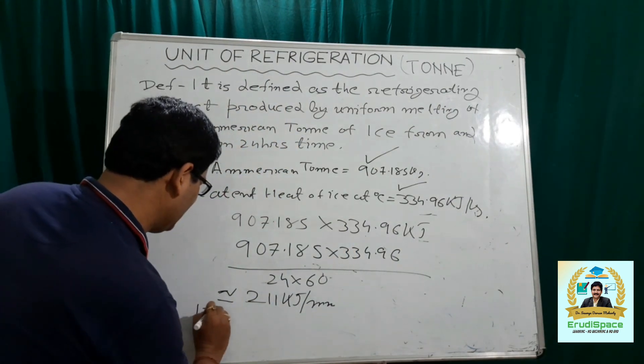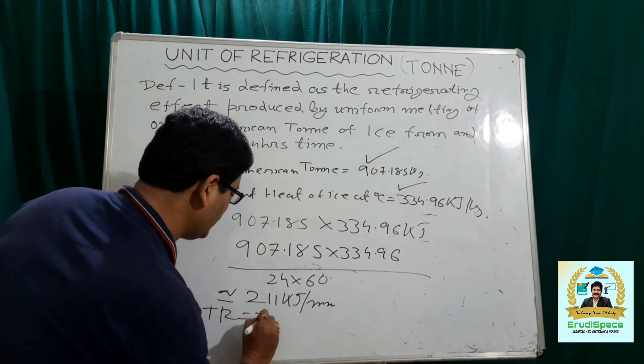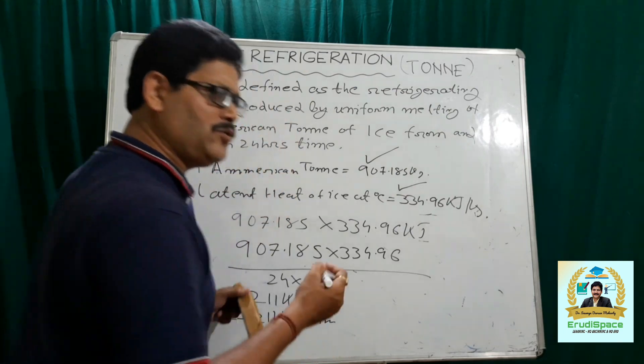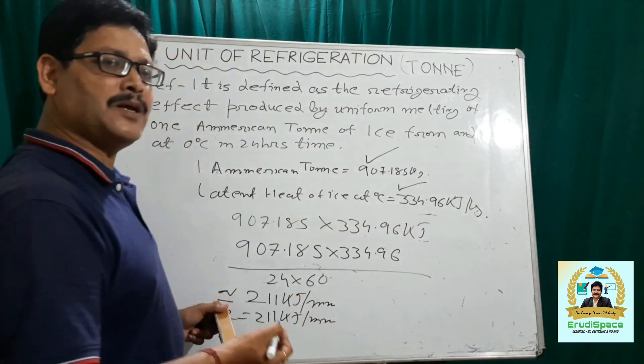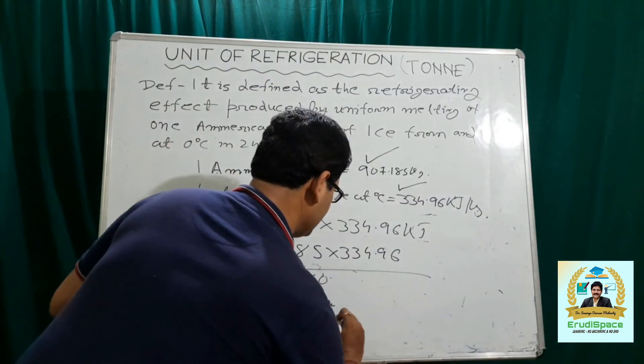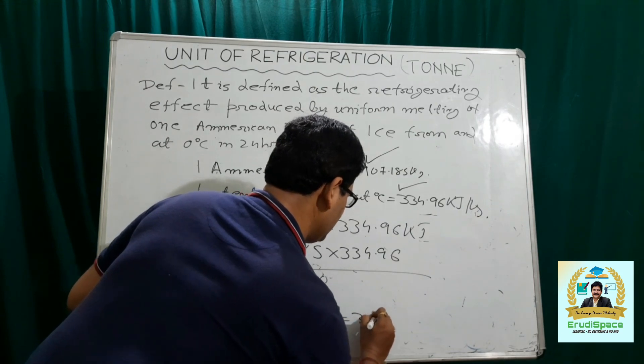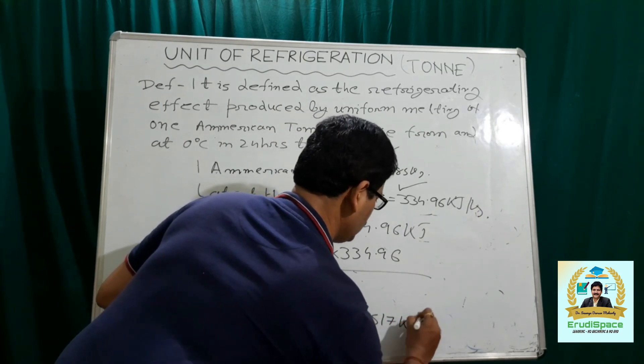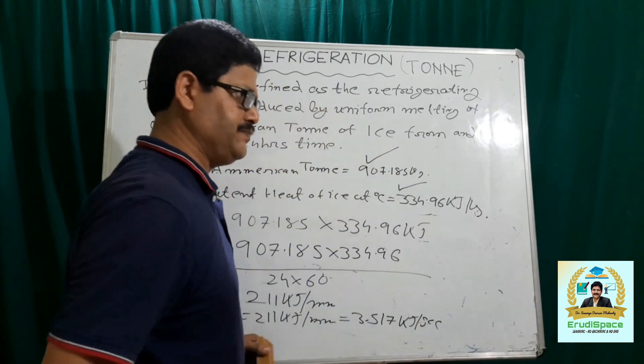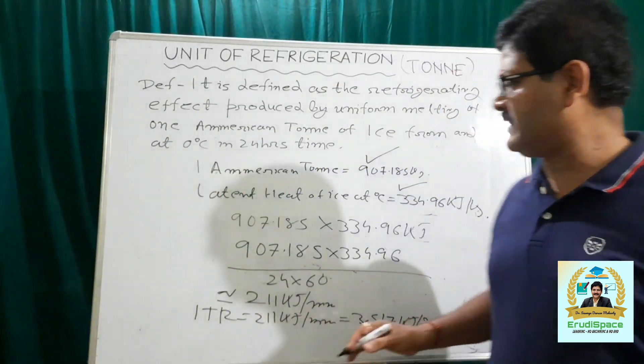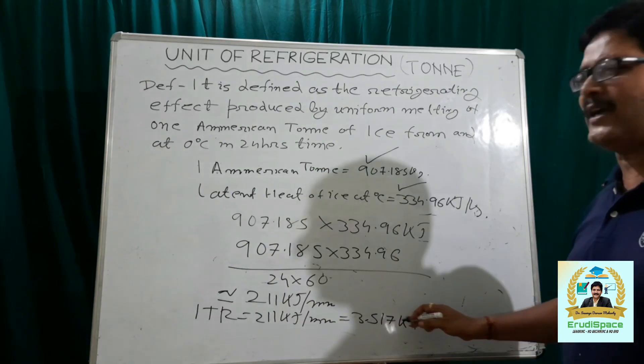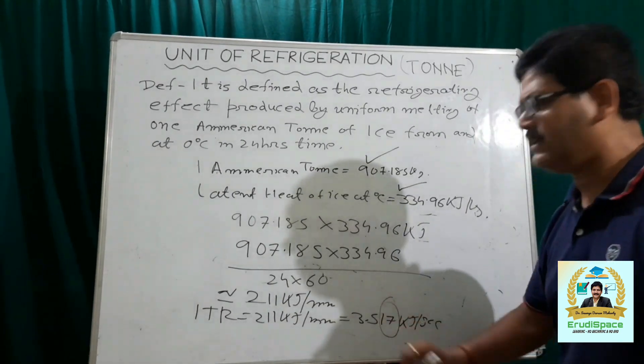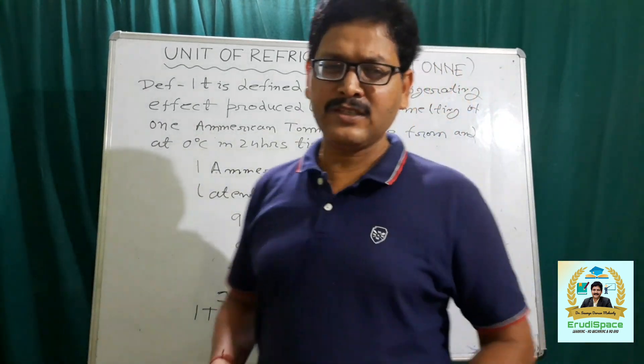So one TR is 211 kJ per minute. If you want to represent this in terms of kJ per second, it is 3.517 kJ per second. Some people take this as 3.5 kJ per second, not considering the small fraction.